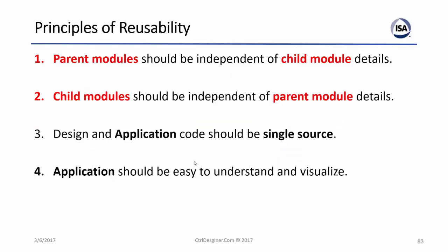But let's come up with some rules: the parent module should be independent of the child module. For example, if I have a child module of a pump, then my distillation doesn't need to know whether the pump valve is opening or whether the temperature is high or low. The parent module needs to say the pump should be ready, or not ready, or running, or should stop. Not ready and stop are the majority of the time the same.